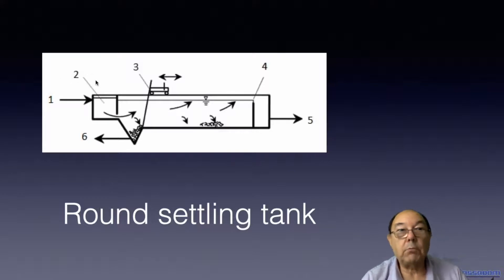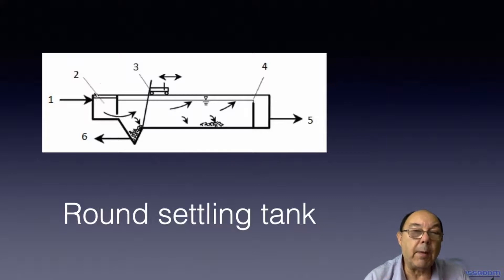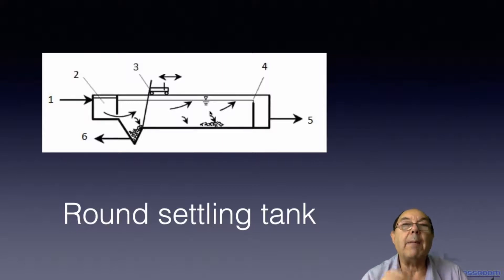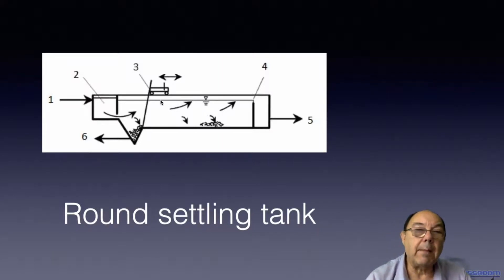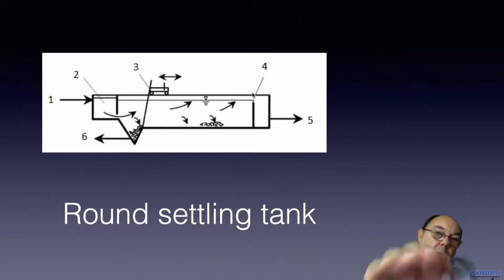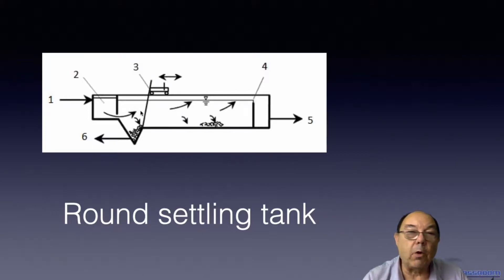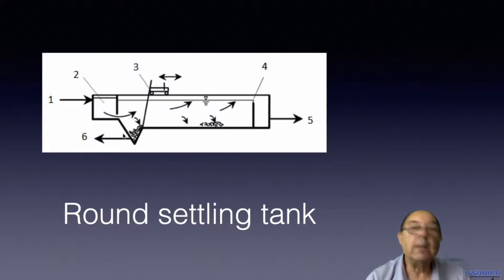Water comes in here and there's a baffle that will reduce the amount of turbulence, because one of the things that's essential for all these types of settling tanks or clarifiers is that we have laminar flow, not turbulent flow. Laminar flow means that all the flow is in layers, all going in one direction with no turbulence. By getting laminar flow you'll get good settling, and then the sludge can be scooped up and taken away.